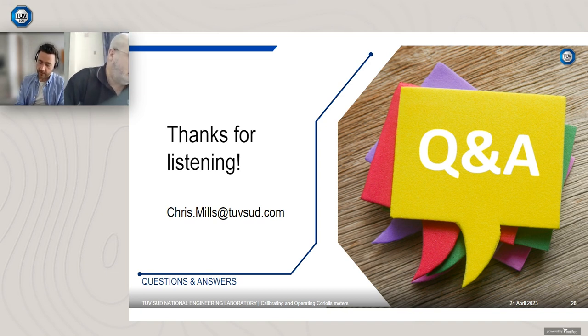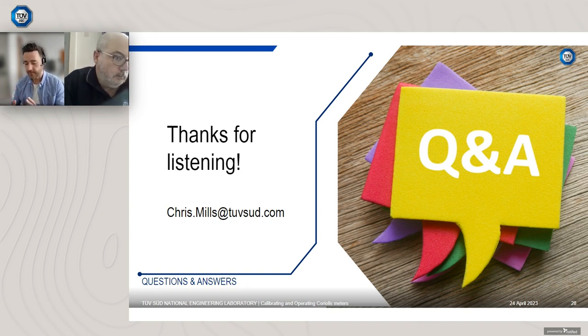Yeah, that's a good question, and a lot of people ask that as well. So that's quite a common question. What we find is there's a trade-off between high viscosity, or a correlation between high viscosity and Reynolds number effect. Now, a simple rule of thumb, we normally say it around about 50 centipoise. Above 50 centipoise is what we call medium to high viscosity, and that's when you start to notice the Reynolds number effect. At 50 centipoise, if you calculate your Reynolds number, depending upon the velocity that you're operating, you might be starting to approach below 10,000 Reynolds number when that Reynolds number effect becomes apparent.